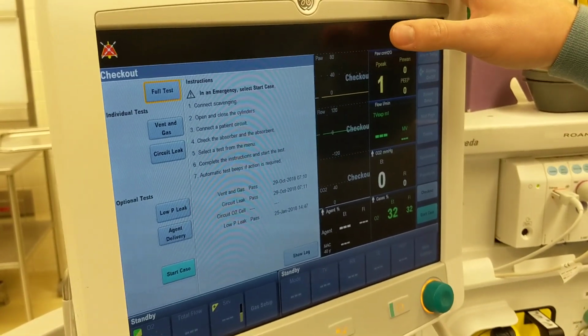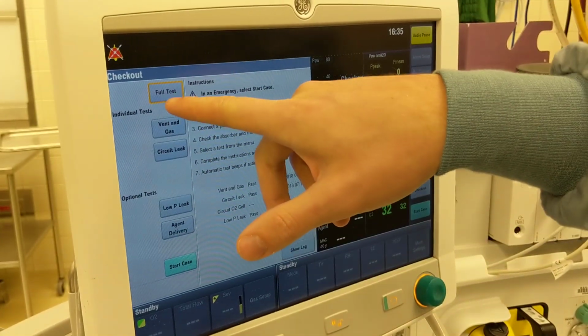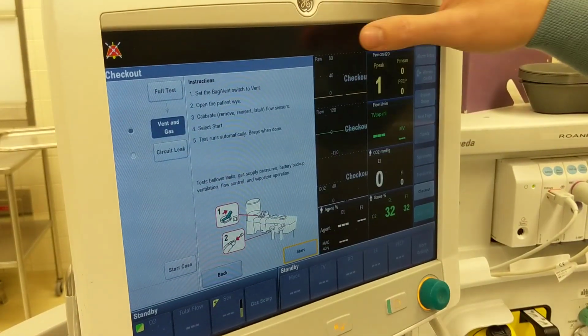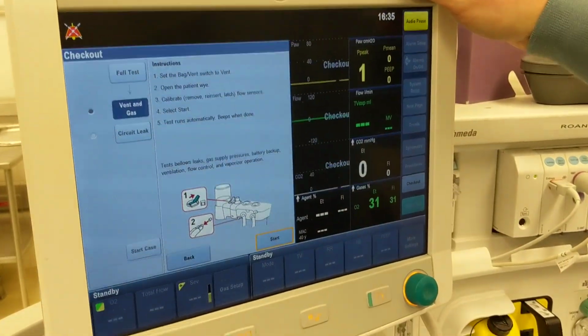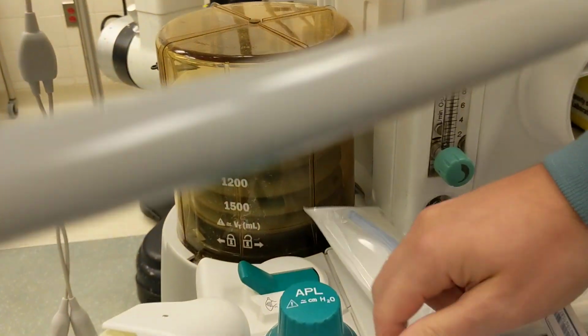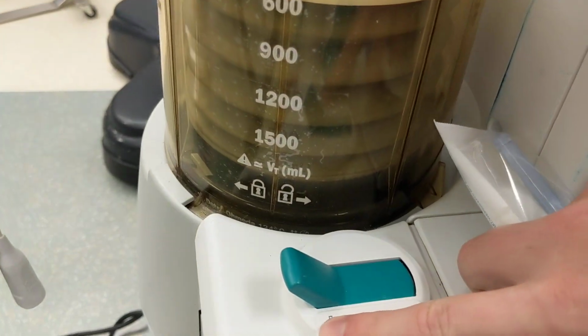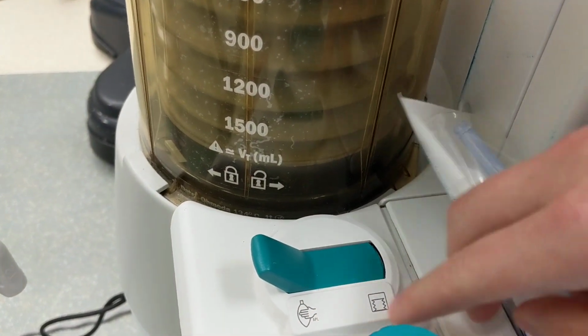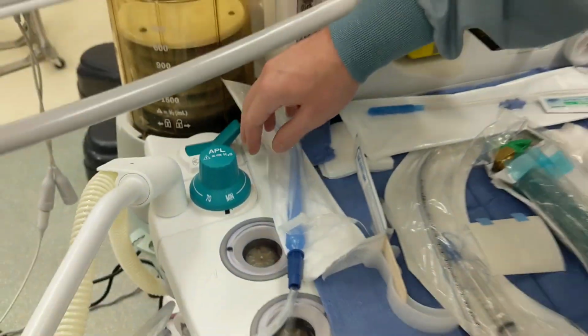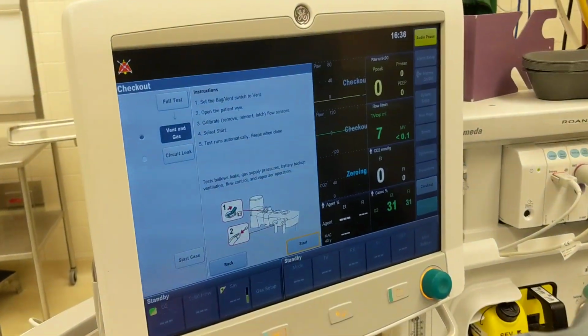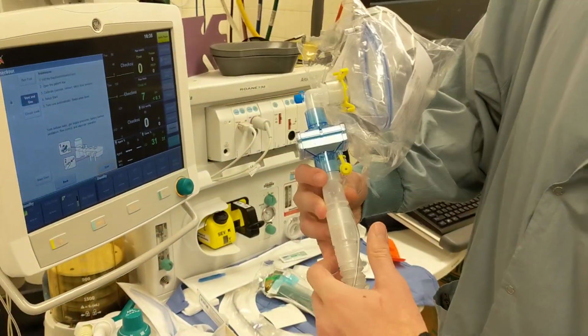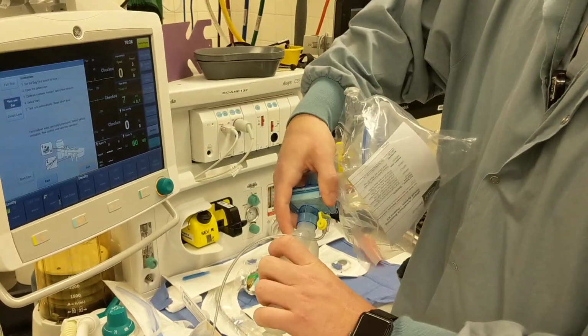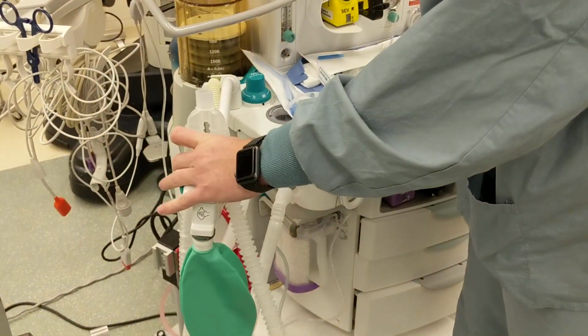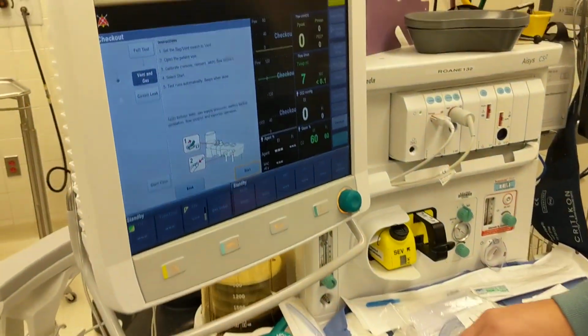So the machine will give you a set of instructions if you just select full test. So first thing is we're going to switch the bag vent, switch to vent. So that switch is here between the bag and the vent setting. Flipping back and forth. That puts us on the vent. Opening up the patient Y. So this is the patient Y here. We're just going to go ahead and open it, keep it open while we do our first step.